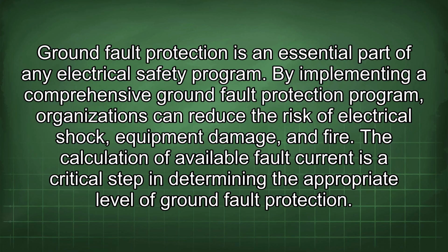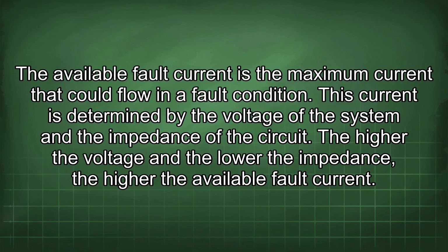The calculation of available fault current is a critical step in determining the appropriate level of ground fault protection. The available fault current is the maximum current that could flow in a fault condition. This current is determined by the voltage of the system and the impedance of the circuit. The higher the voltage and the lower the impedance, the higher the available fault current.